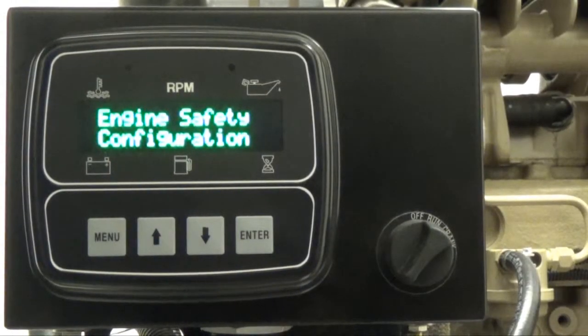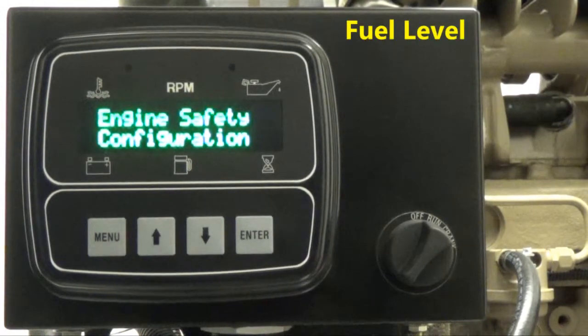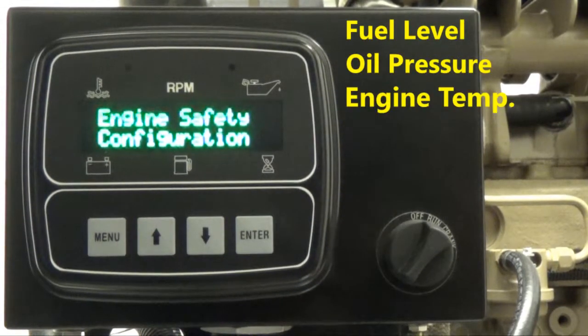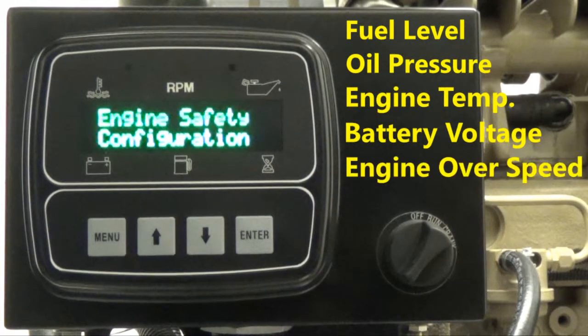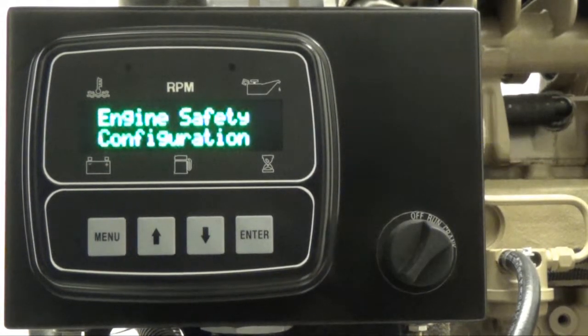In the Engine Safety Configuration menu, you can enable pre-alarms and alarms for the common engine parameters, including fuel level, oil pressure, engine temperature, battery voltage, and engine overspeed. Most electronic engines have oil pressure and engine temperature safeties programmed into their ECU. However, the Controls Incorporated panel can monitor these parameters as well as program them to shut down for values that are more conservative than those designated by the engine ECU.